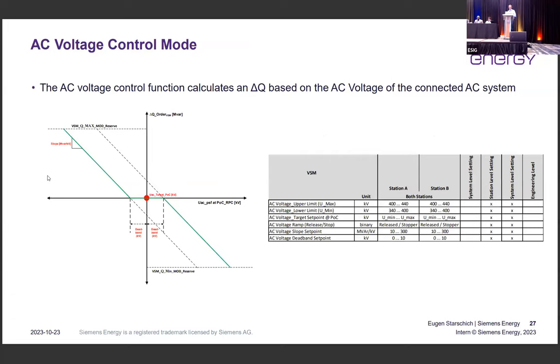One example to make it a little clearer is voltage control. AC voltage control is based on the reactive power, meaning we can change the reactive power based on the AC voltage. This is an input for the operator, with a certain behavior. Depending on the AC voltage, you can change the reactive power. Depending on the network condition, the operator can define a certain dead band where no reactive power should be applied, and then define the slope and the maximum reactive power depending on the AC voltage. So this is the flexibility that the operators have. As I said before, all this flexibility is available, and now it should be utilized.